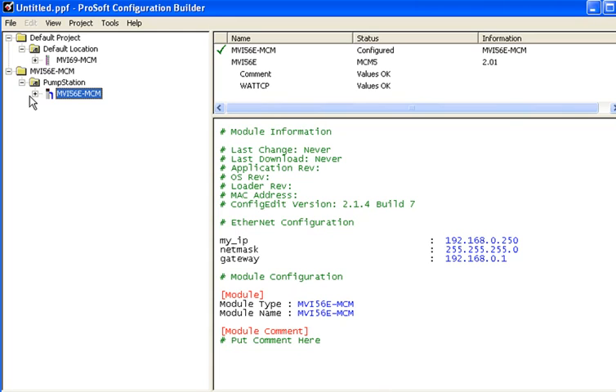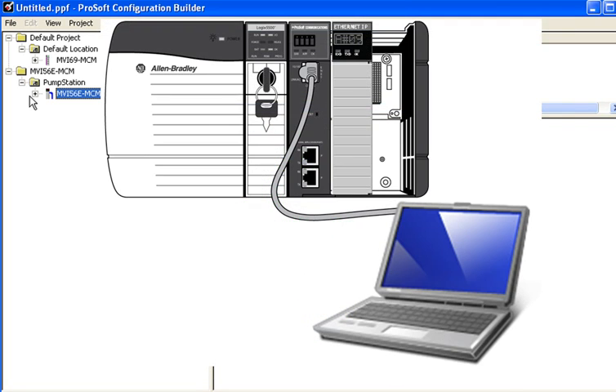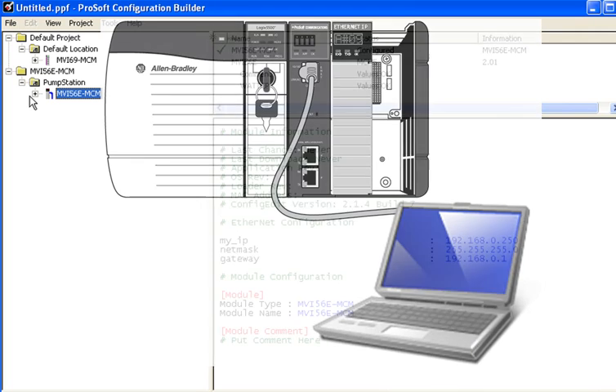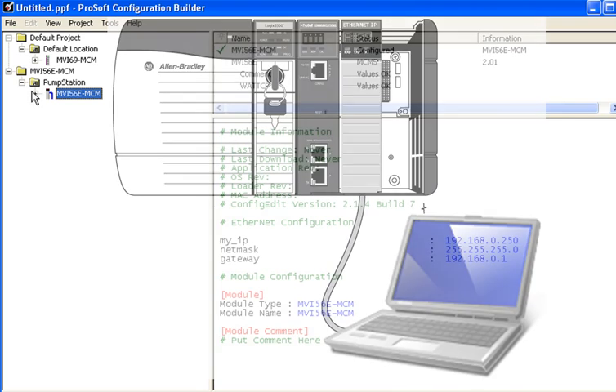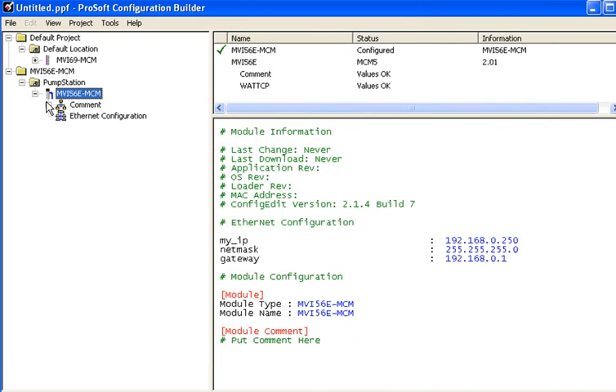Now we'll set up the MVI-56E-MCM and get ready to go online. The PC running the PCB software can go online with the MVI-56E using one of the following methods. First, the PC can directly connect to the Ethernet port on the MVI-56E. And the second option is to bridge through a 1756 ENBT module within the ControlLogix rack. This is handy when other Rockwell Automation networks are being used and bridging is required.